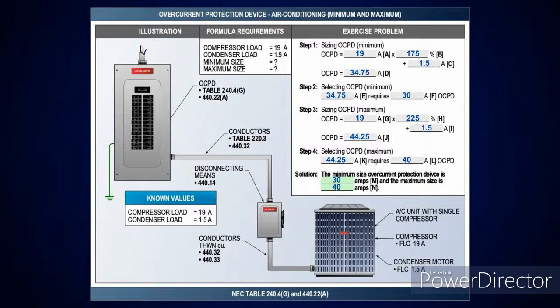Now, as I was saying, when you get to the 2023 code and read that, they have an exception 1 and exception 2, which reads like what it used to be in 430.52C1 that deals with motors. Okay. So when you look at 440.22A, it says you can take it at 175%. And it says if it won't start, you don't even have to do another calculation. You can go up to the next size. And then exception 2 says if it still won't start due to inrush current, then you can take it at 225%.